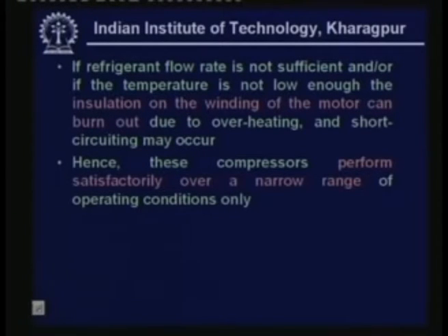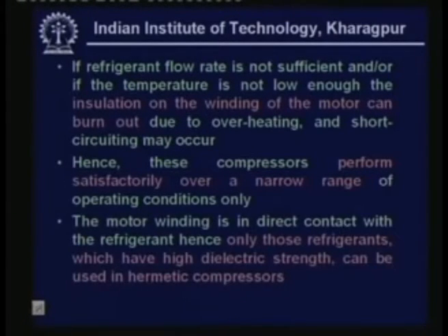So normally hermetic compressors are not used over a wide range of operating conditions. They work satisfactorily over a very narrow range of operating conditions. And as I have already explained, the motor winding is in direct contact with the refrigerant, and hence only those refrigerants which have high dielectric strength can be used in domestic refrigerators. I mean, in hermetic compressors you cannot use all kinds of refrigerant. You have to have good compatibility between the winding and the refrigerant.